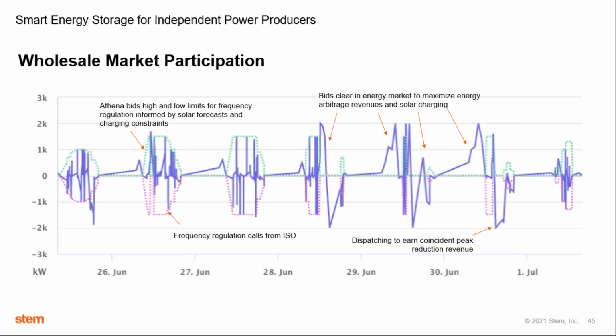There are also times, say in the middle or some days toward the right, where there's no bid in frequency regulation, so the dotted lines are at 0, yet the generator command still goes up and down. That's because at those times we're transacting in the energy markets. There are a few reasons we'd do that: one is to arbitrage energy prices, another is to charge the system up to a high state of charge so we have the opportunity to take advantage of a real-time price spike.